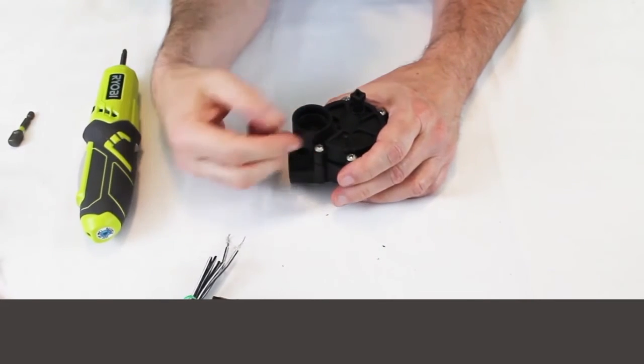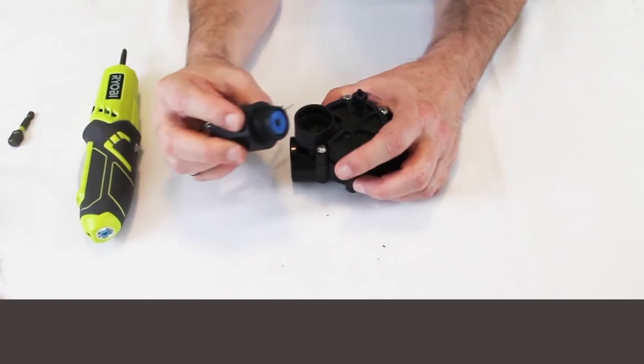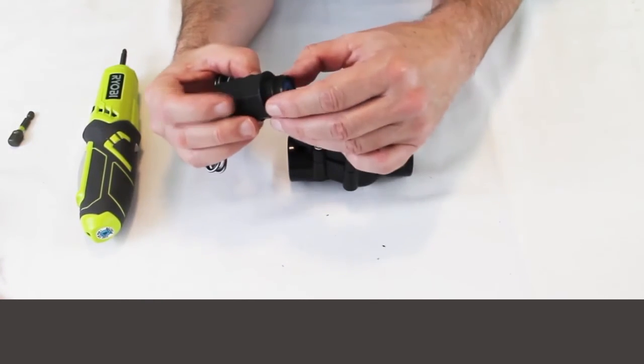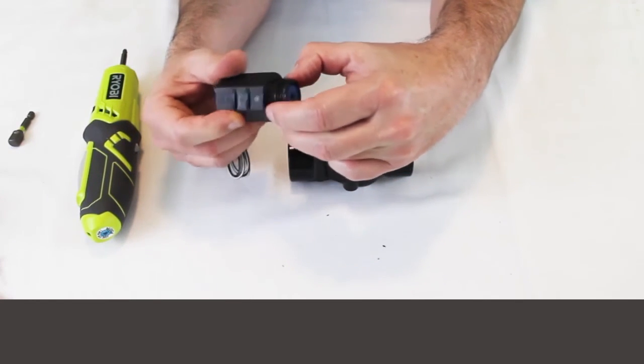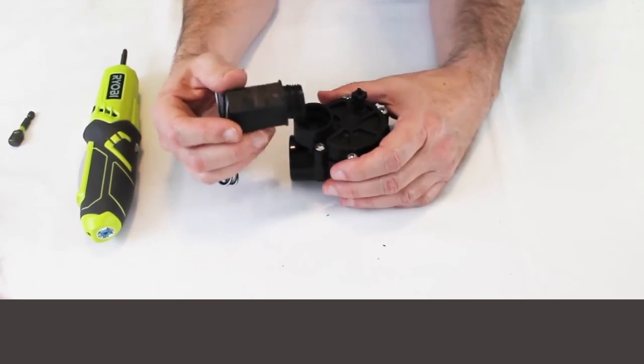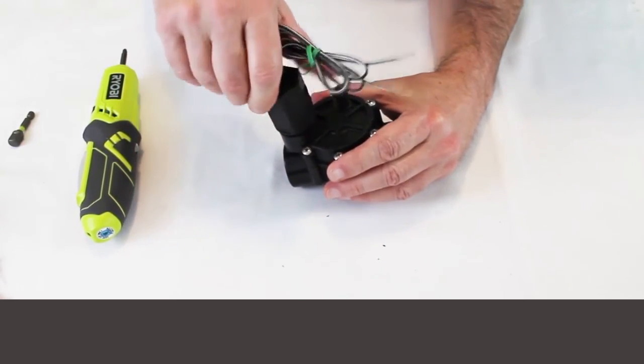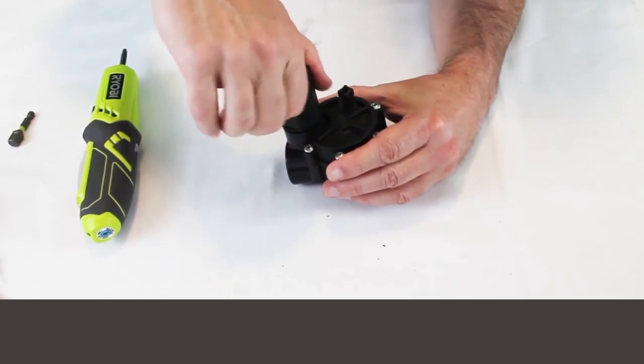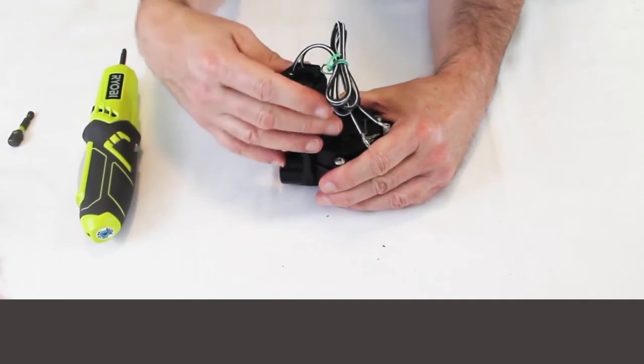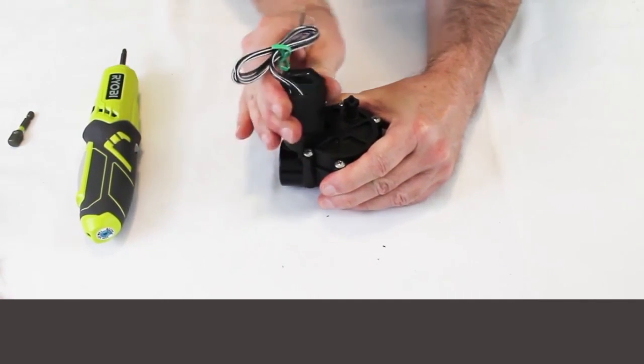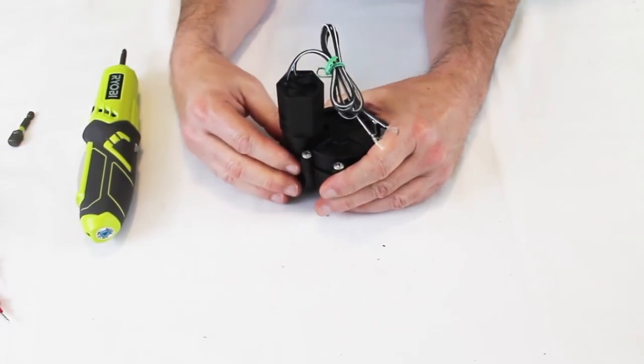Now if we were rebuilding it in the field, I'd probably take some more water and just make sure I flush this out before I put this back on. On this one there's a little bit of an O-ring around here, so you'd want to inspect this and always be careful. On this one it's not such a big deal, but on other valves when you thread this back in here on some valves, it's easy to cross thread, especially if you're hanging upside down in a valve pit or something, rebuilding these. Just take your time and make sure that everything goes on good and you're not stripping out any of the plastic threads. And there we go.